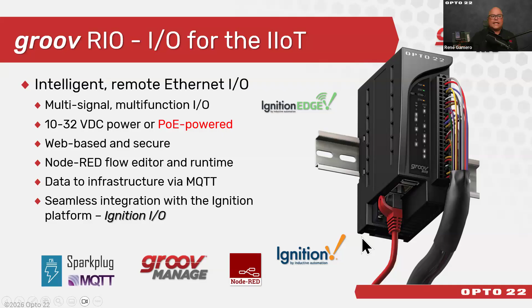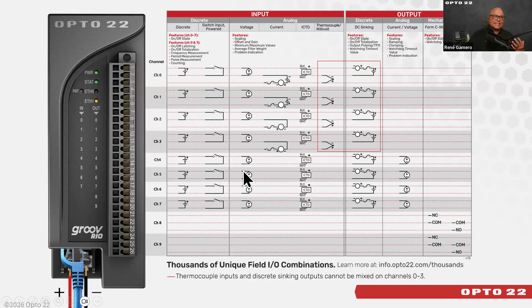You can run Ignition Edge here. This becomes, because it has dual NIC cards, your secure segmented network way of not only contextualizing your data, but protecting it behind this physical firewall while it publishes it up to a broker to be digested and analyzed with Ignition. Here you can see all the different IO points, they're software configurable. Depending on how you wire them, they can be inputs or outputs, digitals or analogs, current or voltage, thermocouple, ICTD, physical contacts, etc.